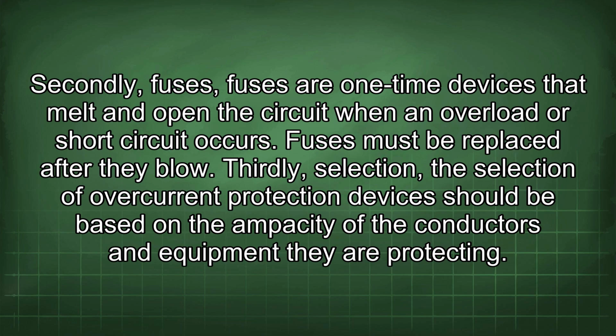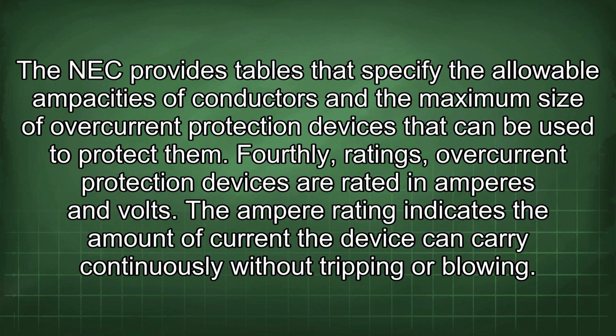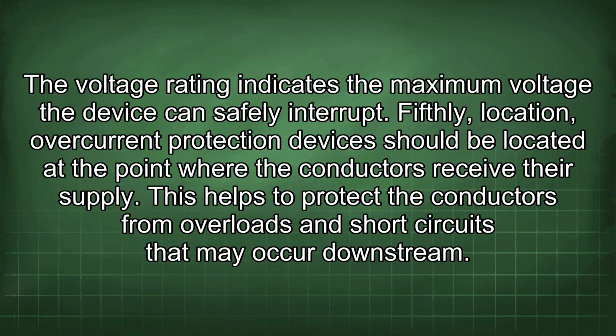Thirdly, selection. The selection of overcurrent protection devices should be based on the ampacity of the conductors and equipment they are protecting. The NEC provides tables that specify the allowable ampacities of conductors and the maximum size of overcurrent protection devices that can be used to protect them. Fourthly, ratings. Overcurrent protection devices are rated in amperes and volts. The ampere rating indicates the amount of current the device can carry continuously without tripping or blowing. The voltage rating indicates the maximum voltage the device can safely interrupt.